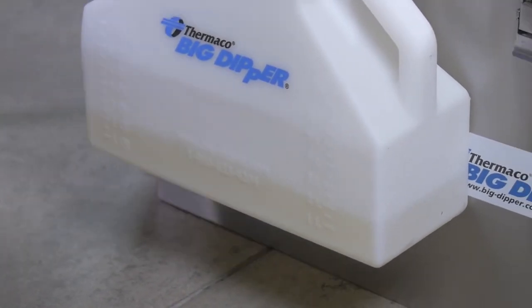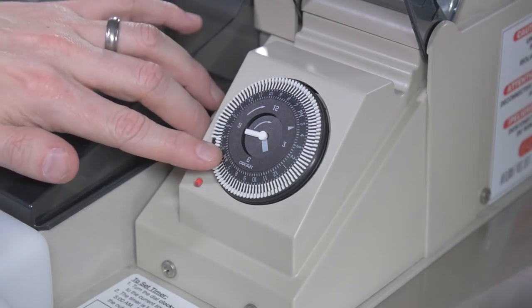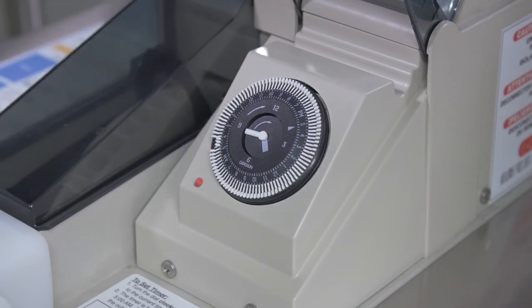Ideally, there should be little to no water in the grease collector. If there's a significant amount of water in the collector, decrease the run time by moving one of the inner tabs to its outer position.